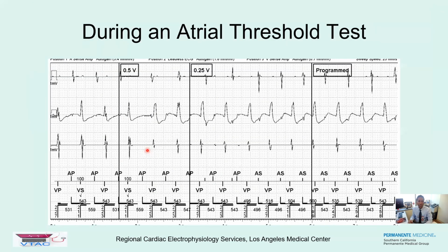So the most common scenario you might see is if you're doing a threshold test. This is important - say you're doing an atrial threshold test in the ER, and here you see we're pacing, and then we come down to 0.5 volts. When I give an A pace, this A pace doesn't capture the A. See this A pace?